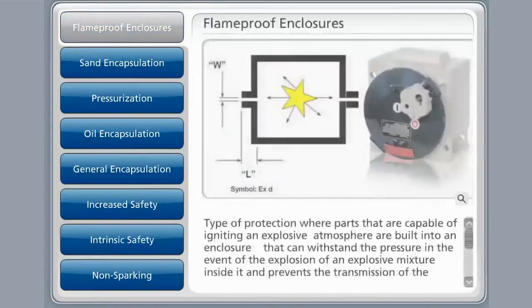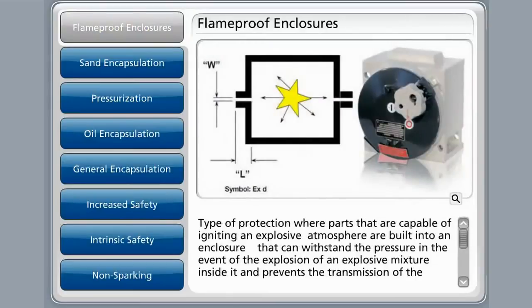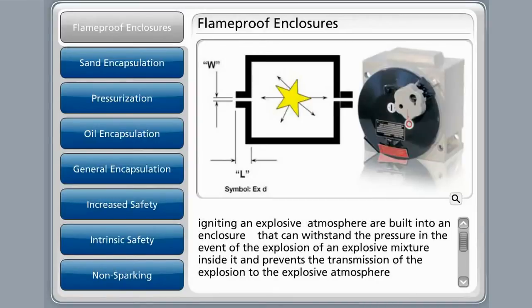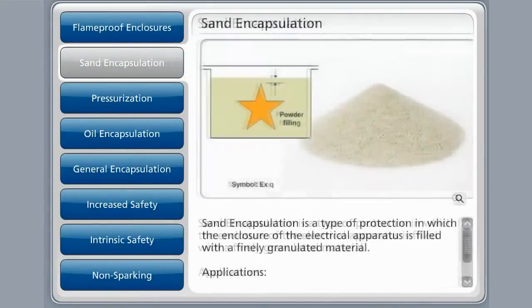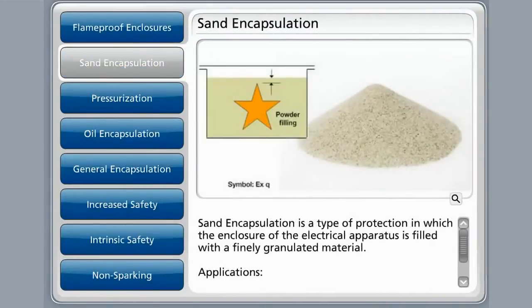The flame-proof method is a type of protection where devices capable of igniting an explosive atmosphere are built inside an enclosure. This protective method prevents the transmission of the explosion to the external atmosphere surrounding the enclosure. This method would be suitable for applications on power-operated equipment, switchgear, motors, and any equipment that produces an ignition source during normal operation.